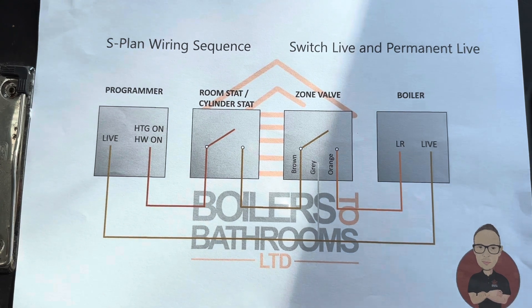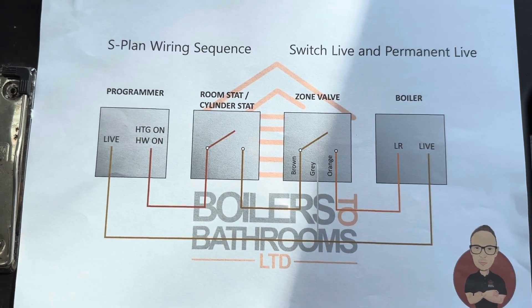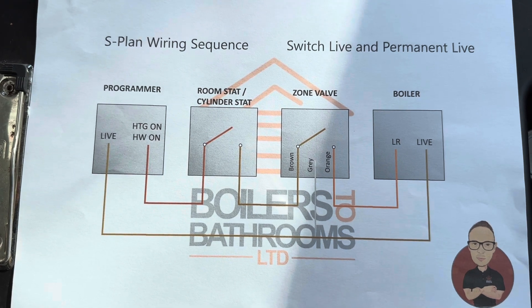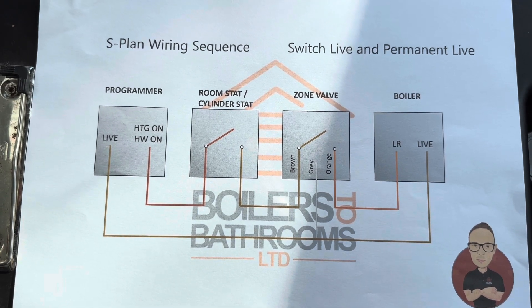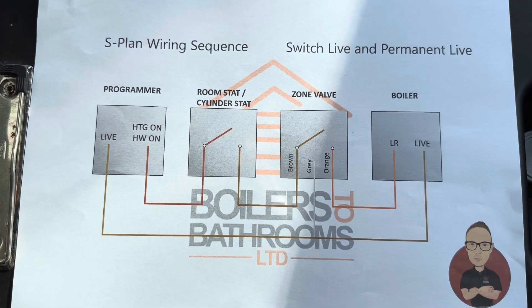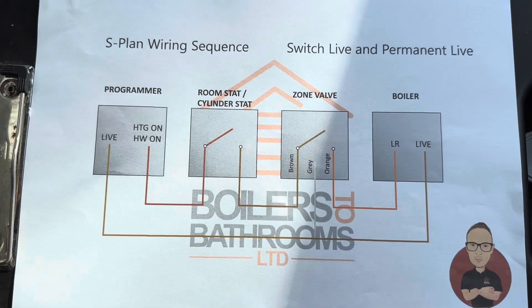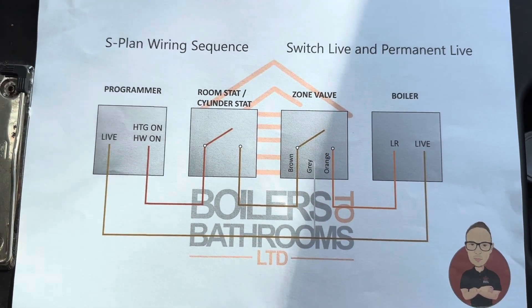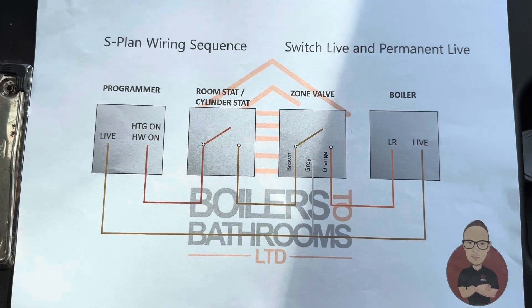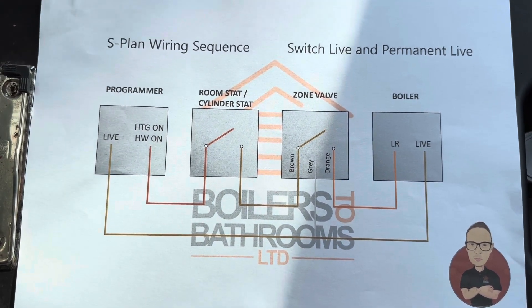The good thing about S-plan is it doesn't matter whether it's your heating zone valve or your hot water zone valve because the process is still the same. It has to go from your programmer to your room stat or cylinder stat, then to your zone valve, then to your boiler. The colors on the cables don't change — it's basically just depending on what rooms and cylinders you have and what programming you have.